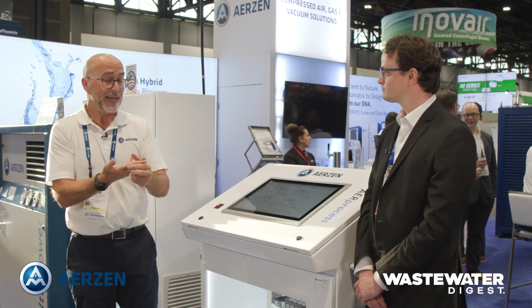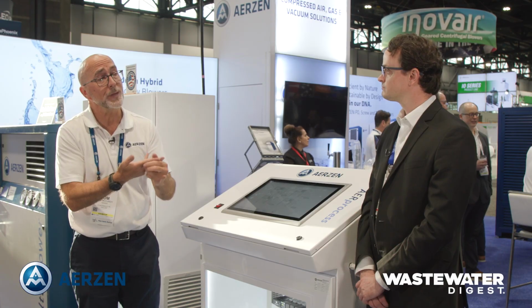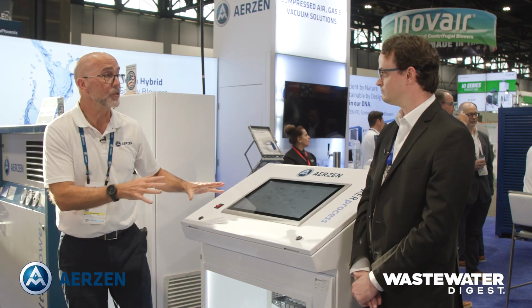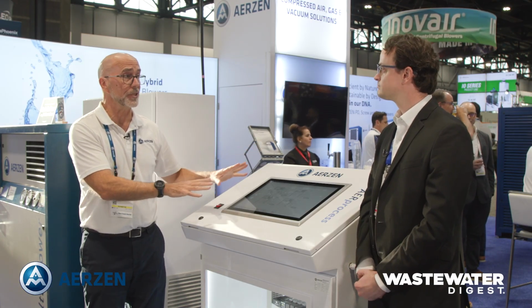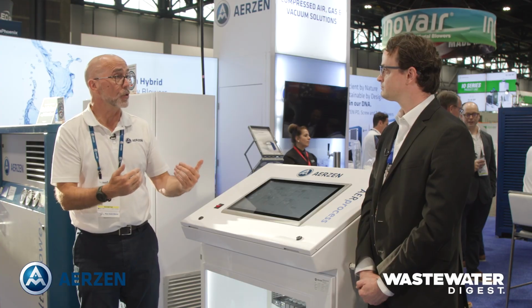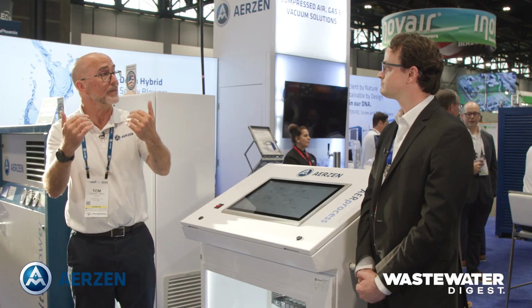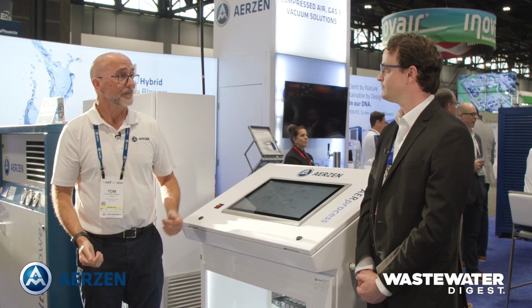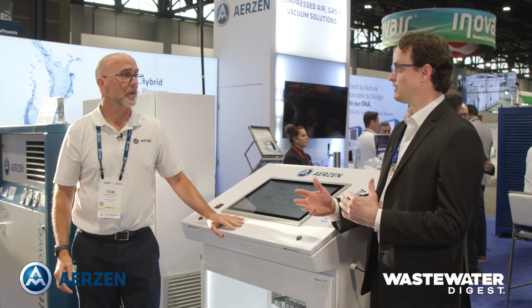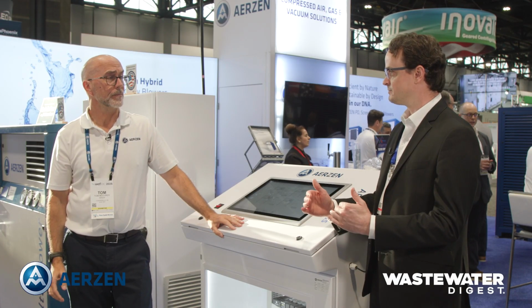So this manages the sequencing of the blowers. It utilizes the most open valve flow-based type system, and it is what they call a self-tuning algorithm, which basically learns the variables in the system and responds accordingly. It doesn't over-aerate, it doesn't under-aerate. Yeah. Well, and you're talking about a lot of these small minor improvements.